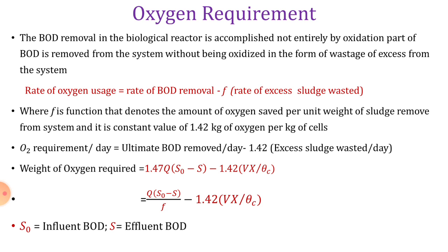O2 requirement per day is equal to ultimate BOD removed per day minus 1.42 times excess sludge wasted per day.